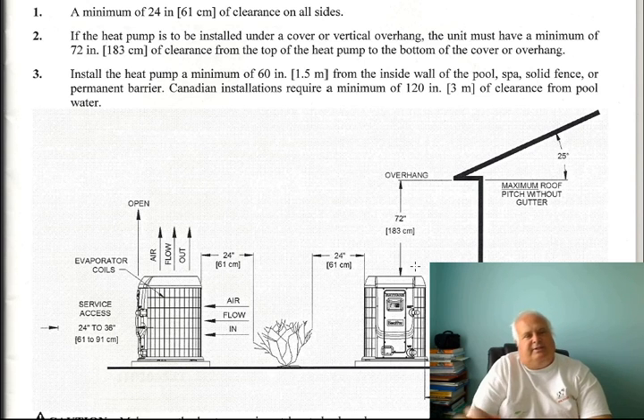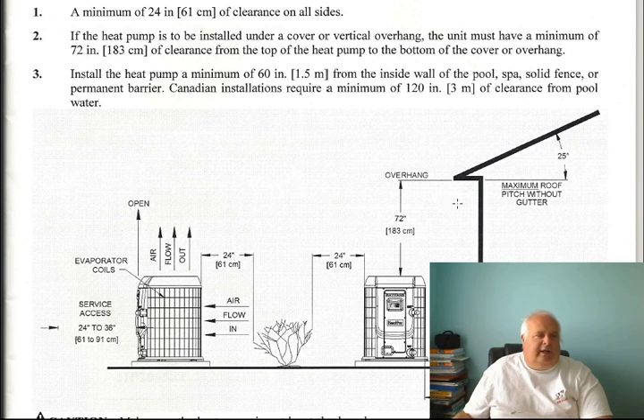Hey Harvey, why am I burning out fans? Look above, look at your environment, and you're right at the roofline. Again, you want to be 24 inches away from anything that's from the coil.